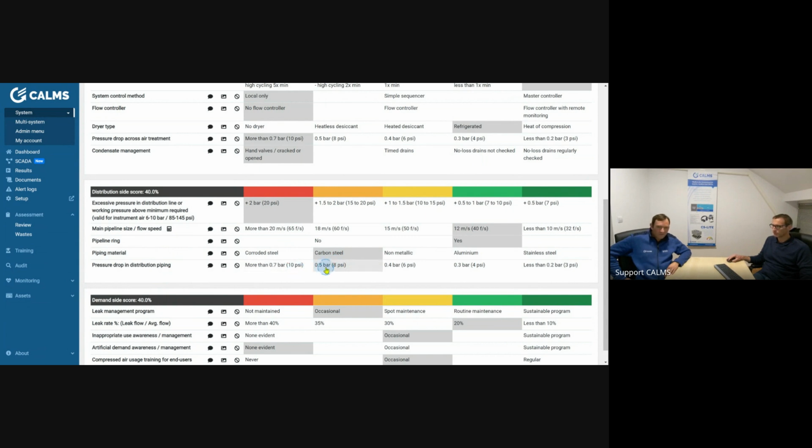I don't know, but in the ring, I don't think there's a problem in the ring. But I mean, in the main pipe to the ring, is there a problem? Maybe there might be a pressure drop already, or not. It's big, but we used to have this problem with the small pipe where the VSD is, but now we put it to 3-inch. So you don't think this is the problem? Okay. I don't think so.